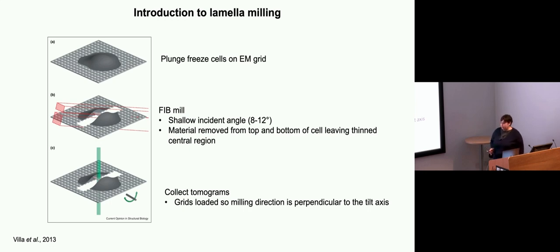So whilst we would typically try to collect as close to possible symmetric tilt series, starting from a pre-tilt to account for this angle, you can become limited by the physical stage tilt of the microscope as well. So that's why it's quite important to come in at these shallow angles.